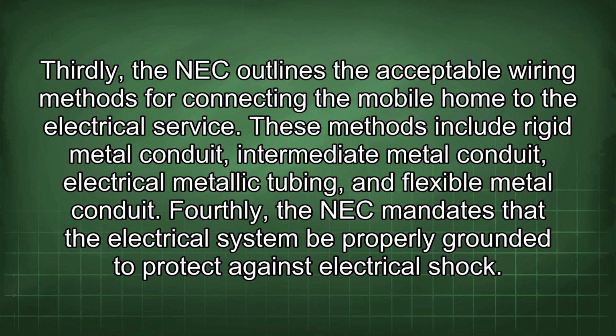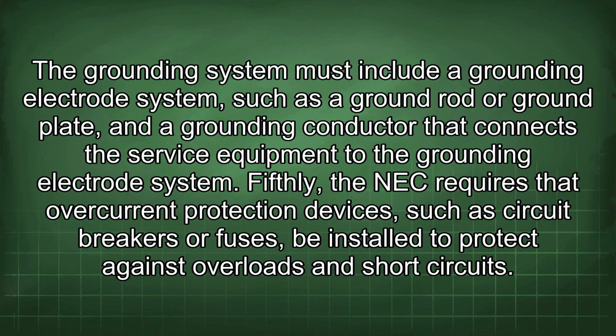These methods include rigid metal conduit, intermediate metal conduit, electrical metallic tubing, and flexible metal conduit. Fourthly, the NEC mandates that the electrical system be properly grounded to protect against electrical shock. The grounding system must include a grounding electrode system, such as a ground rod or ground plate, and a grounding conductor that connects the service equipment to the grounding electrode system.